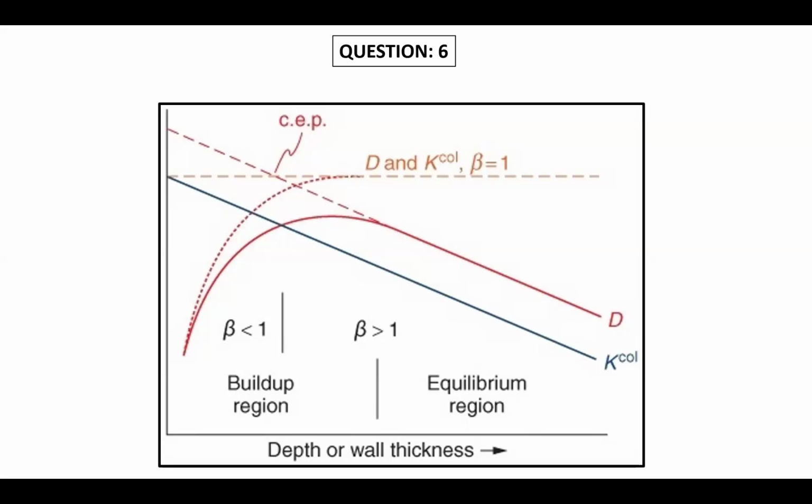So initially, after the beam interacts with the matter, due to the production of the secondary electrons, and after that, the secondary electrons' dose absorption will be there in the matter, sir. So after this, dose buildup will happen until the dose reaches its maximum. Normally it is at the depth of 1.5 centimeters for the 6 MV, sir. After that, there will be more attenuation, so the beam falls off, sir. The absorbed dose will be less. In the kerma, we can say that it is just the energy transfer from the photon to the charged particles, sir. So it is continuous. It is the release of the energy. So the graph will be like this.